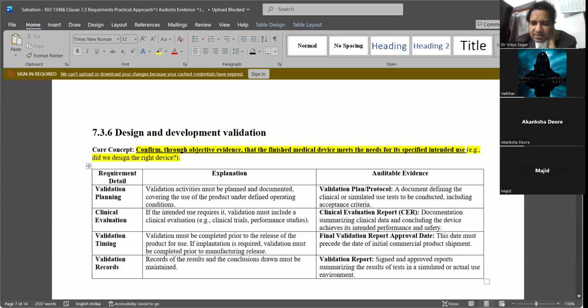Actually, the last that comes is the clinical validation. So after clinical validation, if you are okay with the data, then only you will have the design transfer and other things. Of course, validation reports are important: validation report, final validation report, approval date, clinical validation reports, validation plan and protocol. To me, this is very, very important. Why I say important is, based on your sample size and the statistics, it will dictate a lot of things, your plan and protocol.